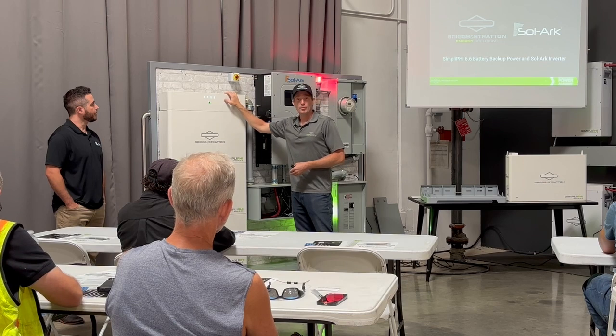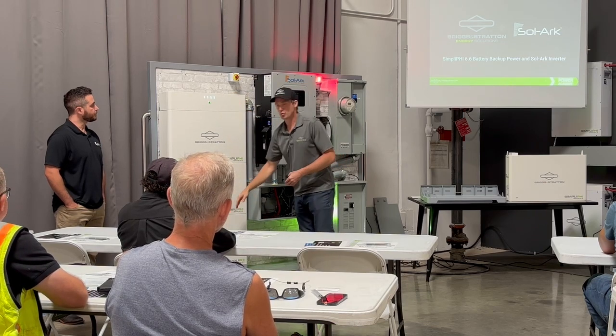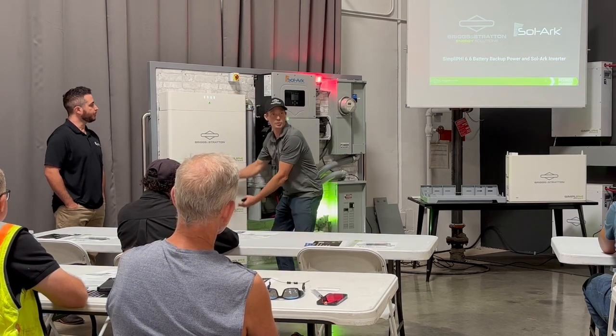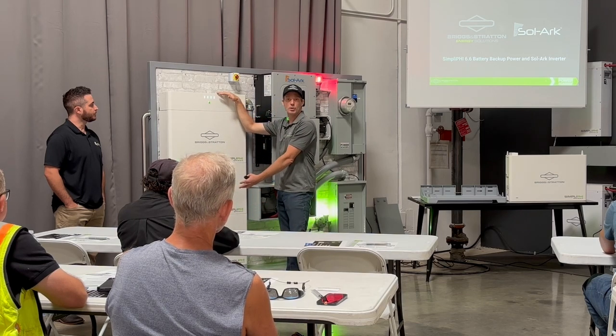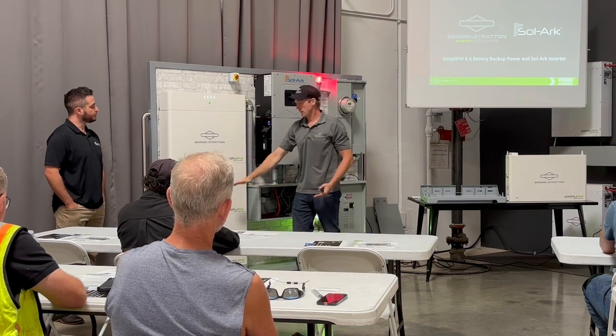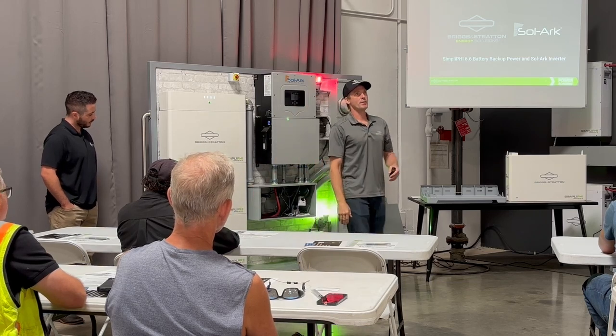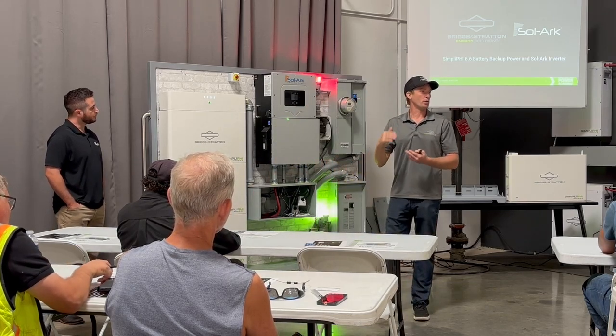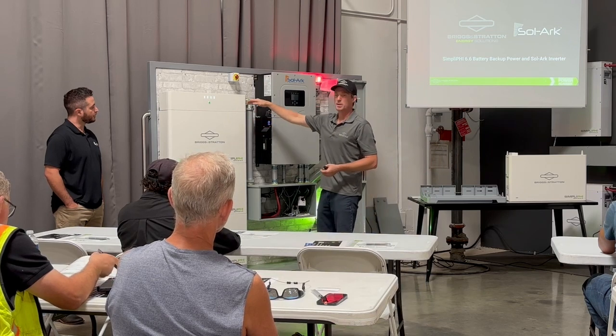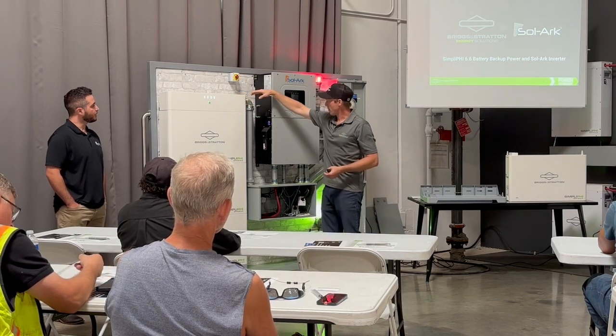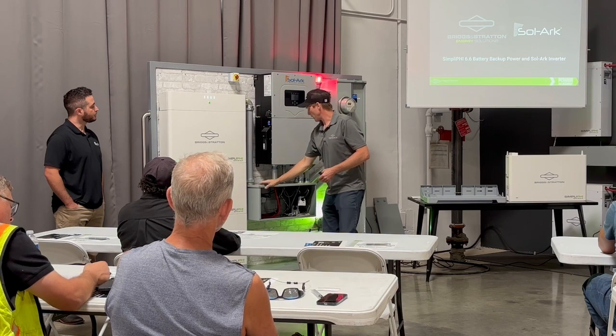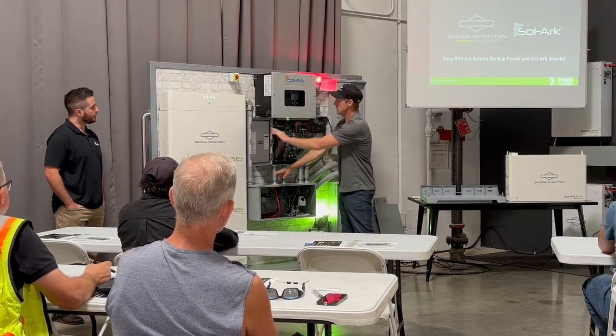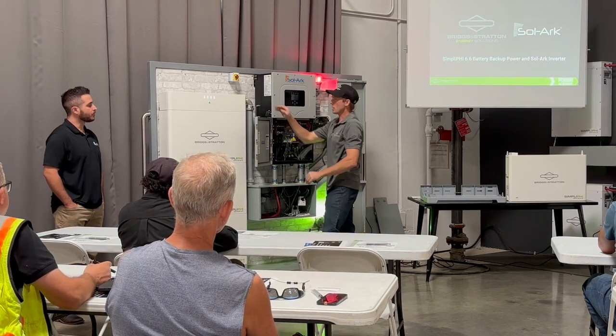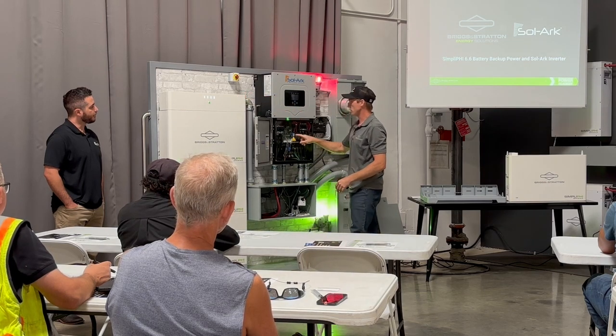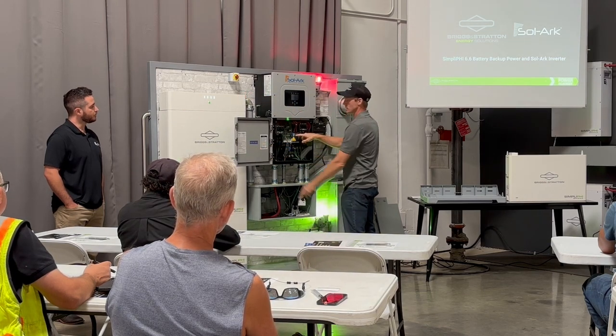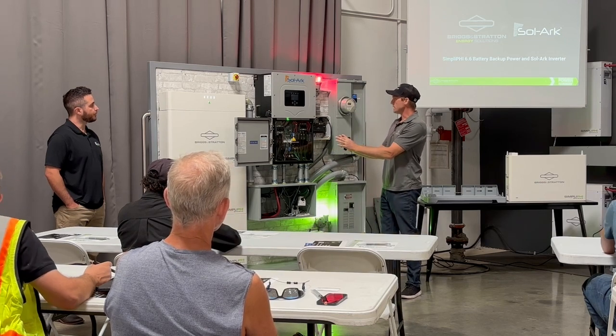So this is a 48 volt battery stack. The batteries are all in parallel. You can have just a single stack of batteries as opposed to a triple stack. So this is 20 kilowatt hours of storage that's here. They come in 6.65 increments, so it's just under a third of 20 kilowatt hours, and that's the limit from NFPA 855 for a stack. And then we're bringing the DC into the Sol-Ark, and so that DC from the battery comes in here. We also have communication coming out of the battery and going into the Sol-Ark, and that's on that blue dongle that you can see here. So that's all the DC side.